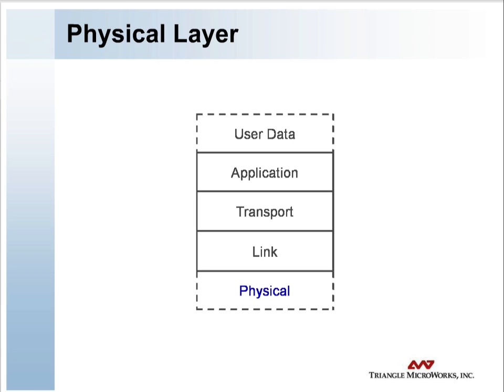The physical layer is primarily concerned with the physical media over which the protocol is being communicated. For example, it handles the state of the media, clear or busy, and synchronization across the media, starting and stopping. Most commonly, DNP is specified over a simple serial physical layer, such as RS-232 or RS-485, using physical media such as copper, fiber, radio, or satellite. More recent applications have implemented DNP-3 over an Ethernet connection.